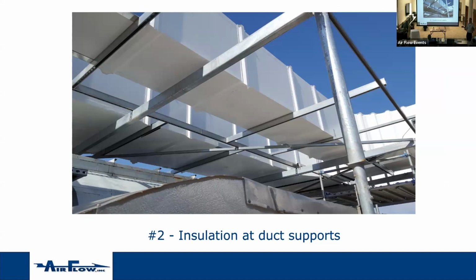So is anybody gonna go in and try it? I don't know. But this, you tape it, we're already insulated. We're most of the way there once it's on the site. And of course, we don't need to wrap it. We don't need to cobble around the structure. If we want to have duct sections right next to each other, we can lay them. You wouldn't lay them right on top of each other, but you can put them as close as you can physically fit them. What's that we go across the seam there, the transverse? What is that, stick out 2 inches? So like 4 inches? Yep, very good, the transverse joint. That is like 2 inches. So as long as you have 4 inches in between, when you start packing everything together to account for.